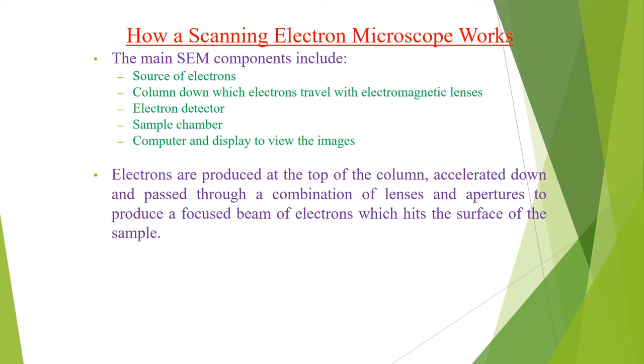Here we will start about how a scanning electron microscope works. The main SEM components include a source of electrons, a column down which electrons travel with electromagnetic lenses, electron detectors, and sample chambers. A computer and display to view the image is also required. Electrons are produced at the top of the column and accelerated down, passing through a combination of lenses and apertures to produce a focused beam of electrons.